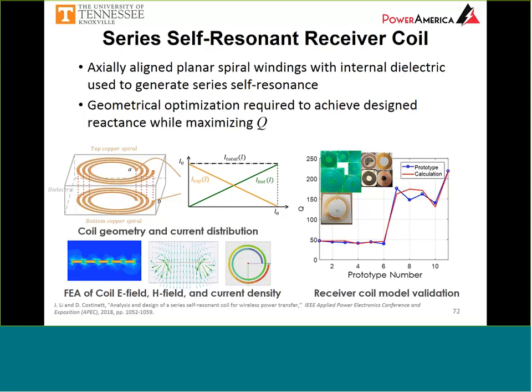One thing we've designed is a series self-resonant receiver coil, a simple geometry with a couple of planar spirals with a dielectric between them. By connecting to opposite terminals on the top and bottom spiral, as current is pushed through it flows once around the spiral and then through the dielectric layer, generating a series capacitance, giving a series resonant characteristic without adding any additional discrete components.